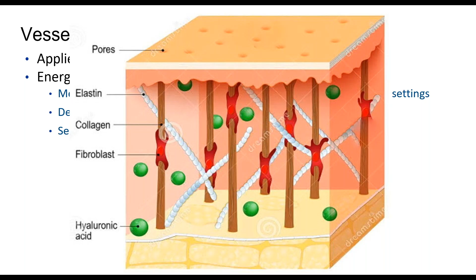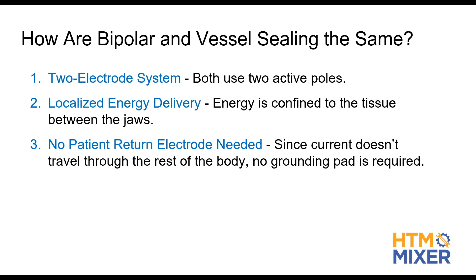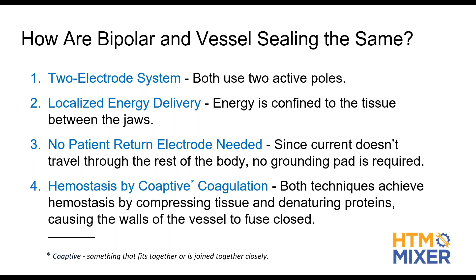Okay, so here's the collagen and the elastin. The collagen gives the tissue strength. The elastin gives it the elasticity. All right, so how are bipolar and vessel sealing the same? Well, they both use, whether it's a forceps or this, two electrodes. We don't have to have a pad. Energy is confined between those two jaws or the two tines of the forceps. No patient return pad needed, and hemostasis by, I learned a new word, coaptive coagulation. Coaptive means something that fits together, is joined together. So both techniques achieve hemostasis by compressing tissue, and that's how it does it.